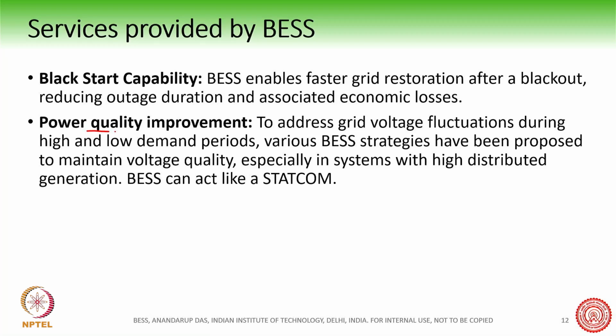And of course there is power quality improvement. The BESS can act like a STATCOM, providing both active and reactive power support. So far we were talking mostly of active power, but a battery energy storage system can also provide reactive power to the grid as and when required. So it can act as a STATCOM, giving both P and Q support to the grid.